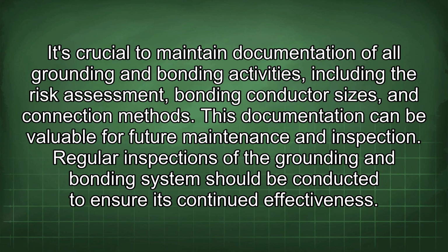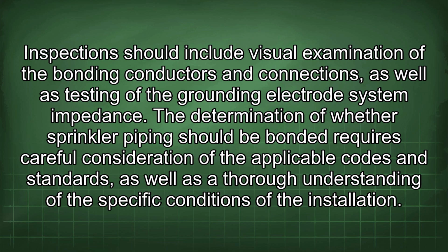It's crucial to maintain documentation of all grounding and bonding activities, including the risk assessment, bonding conductor sizes, and connection methods. This documentation can be valuable for future maintenance and inspection. Regular inspections of the grounding and bonding system should be conducted to ensure its continued effectiveness. Inspections should include visual examination of the bonding conductors and connections, as well as testing of the grounding electrode system impedance.